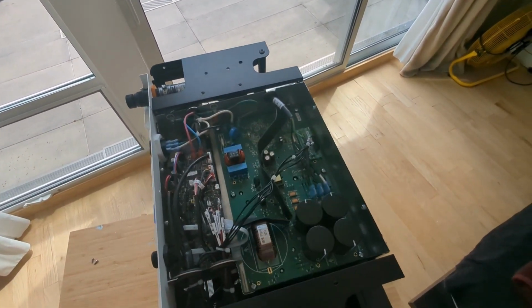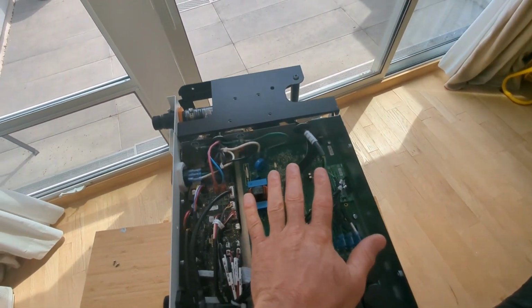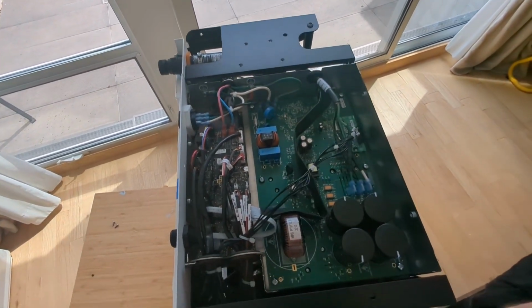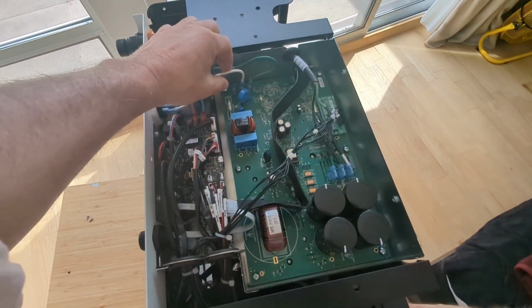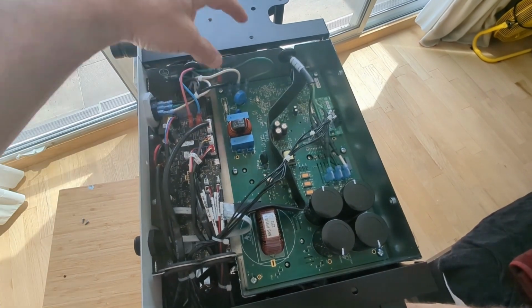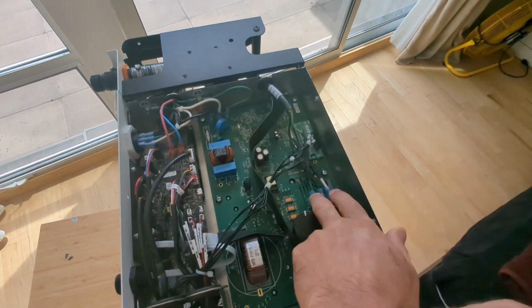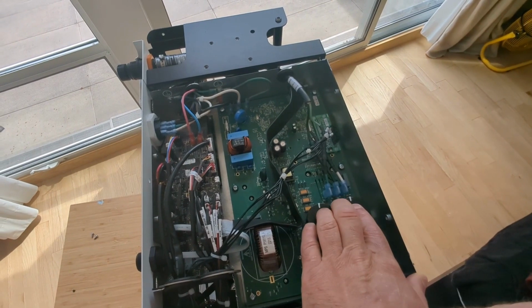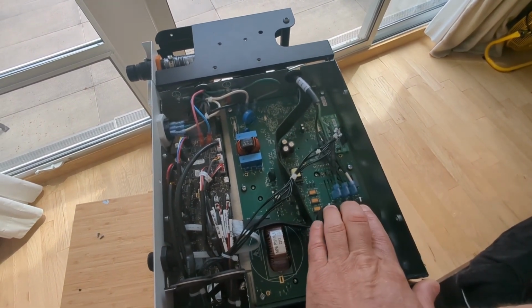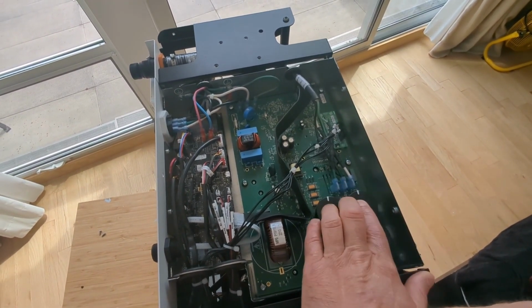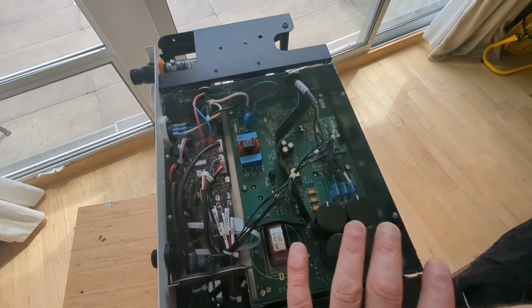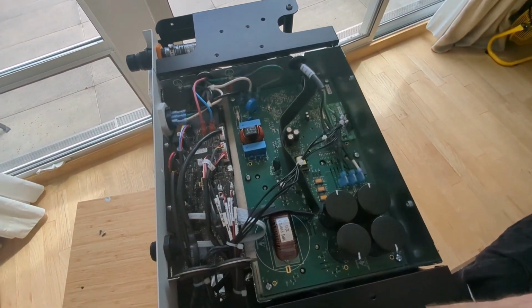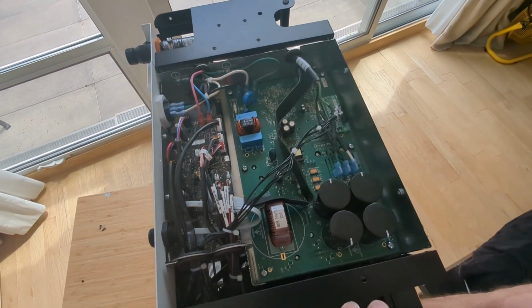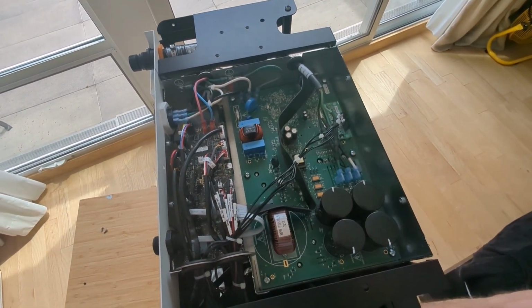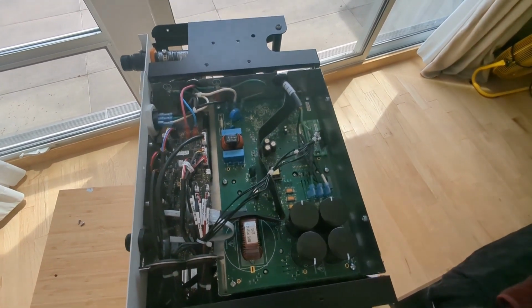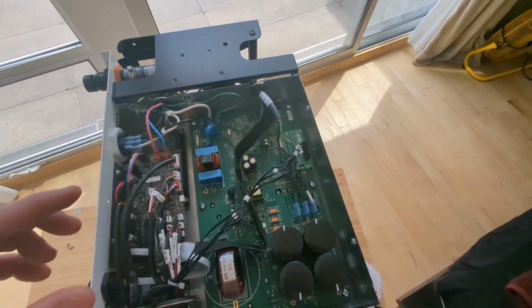This giant board here is the inverter. This board's job is to drive that compressor motor, and it takes 120 volt AC running at 60 hertz in on this side, and it sends out 350 volts on 3 out-of-phase sine waves coming out, and the frequency of this is variable, so it'll change the frequency to change the speed of that compressor motor. That's the entire job of this giant board here. It's a pretty standard board. Some compressors come with them. I don't know if Gradient made their own or they used one of the reference designs, but it's pretty straightforward.